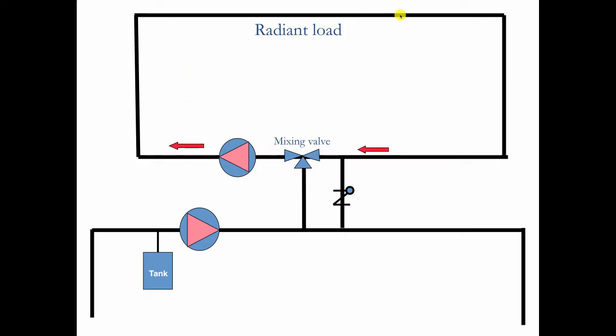So the radiant load is going around here with continuous circulation, moving around and around. We're going to vary the temperature with this mixing valve. There's the primary load, so this is 180 degree boiler water going around here.